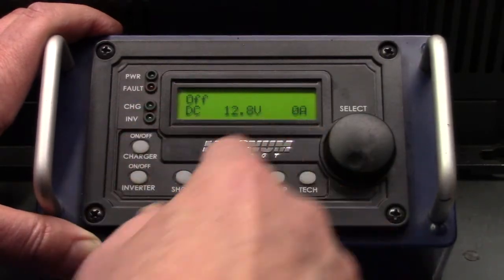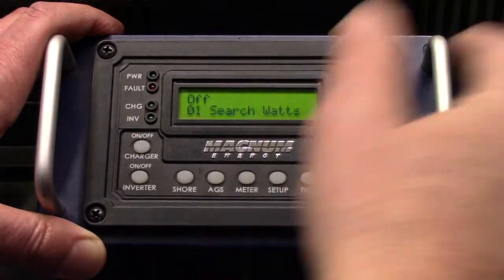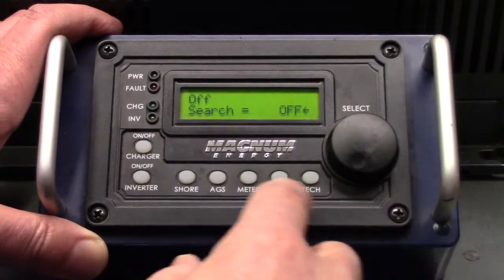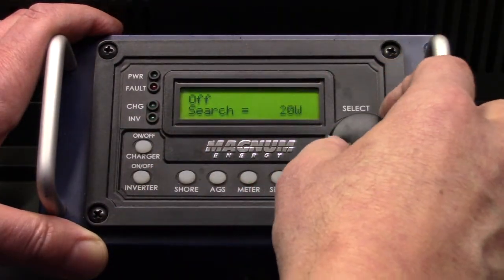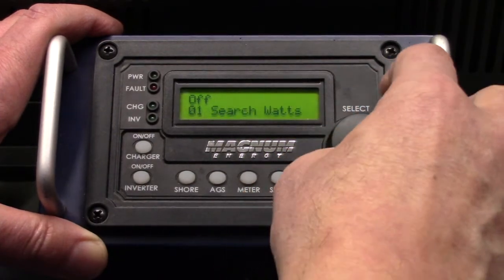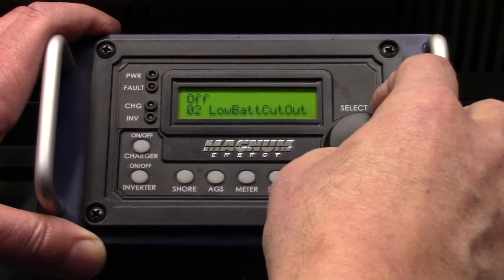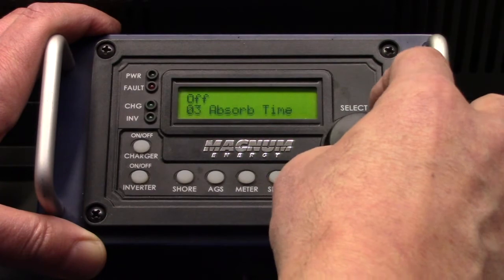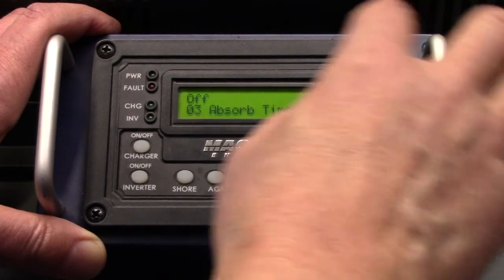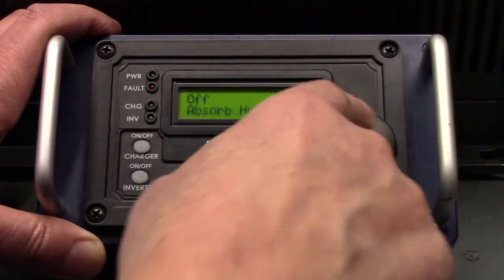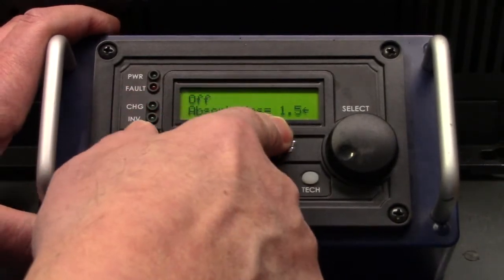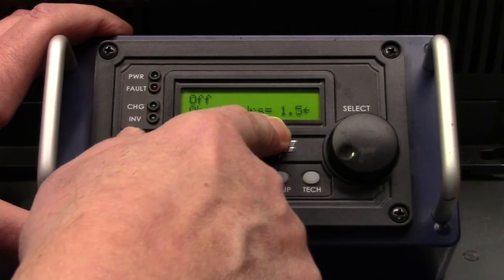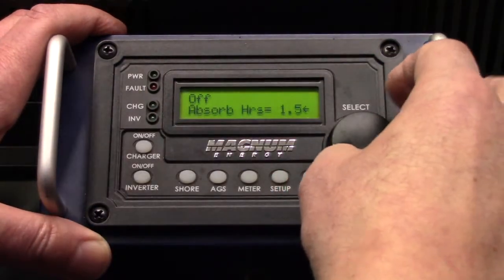Meters, just press the button so you can see the readings, otherwise that's it. Setup's the only one where you've got something to do here. Make sure your search watts is off, then you don't have to worry about it. You want to make sure low battery cutout is at the default, that's fine, don't bother with it. Absorb time, you just got to make sure, depending on how many batteries you have, that it's long enough to get a full charge. Again, 1.5 is fine for your typical 4 battery pack.